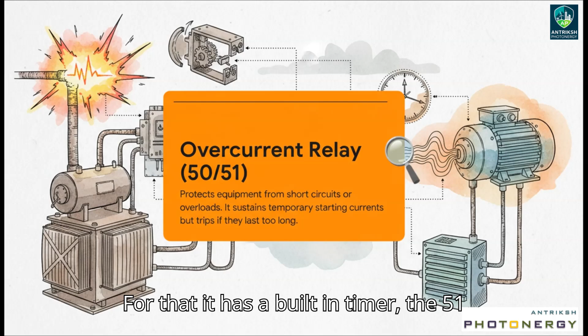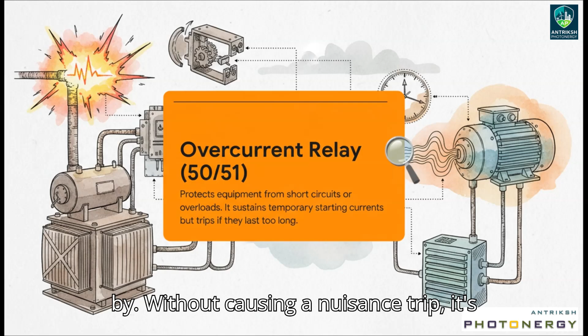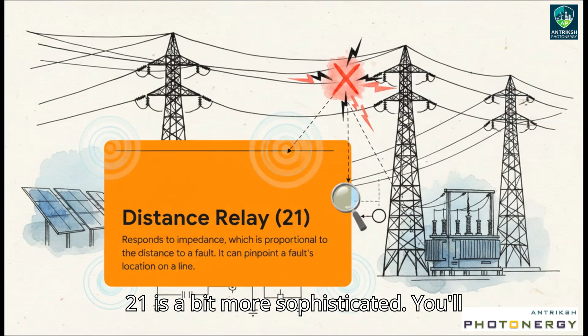For that, it has a built-in timer, the 51 function, that lets that little surge go by without causing a nuisance trip. It's pretty clever. Now, the distance relay, or 21, is a bit more sophisticated. You'll usually find this on the big transmission lines that connect your plant to the main grid.